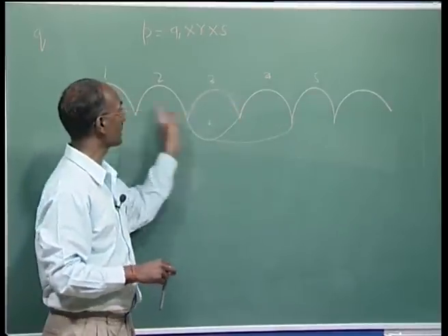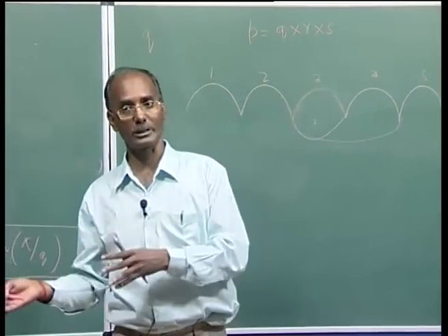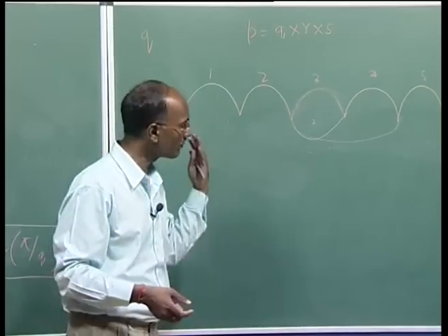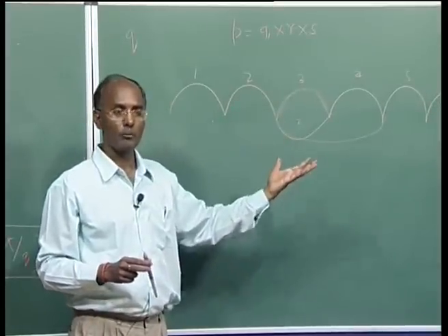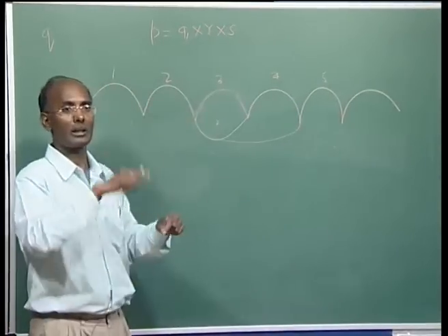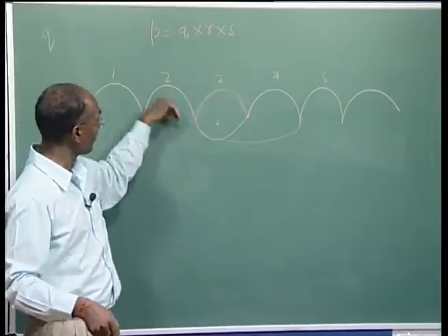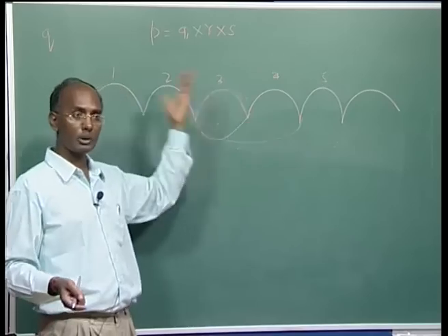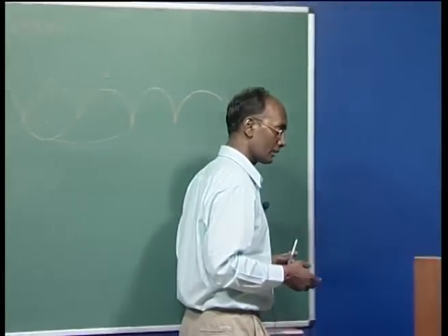So due to this misfire, or the valves not conducting, you can see the waveform is unsymmetrical, and unsymmetrical means more harmonics will be injected into the system. We will analyze later and find that this process is self-curing. We never do anything for this, because after one cycle we are again coming back and completely symmetrical waveshapes are coming, so it is cleared automatically. But due to this, we are getting a lot of harmonics in the system, which is not desirable. So proper protection or proper correction should be done for all these things.